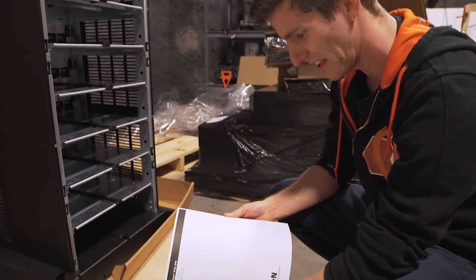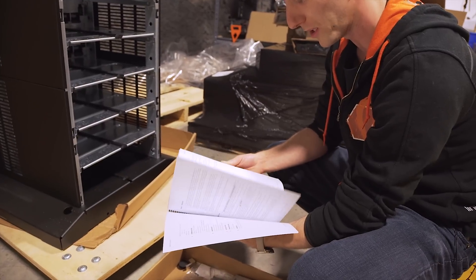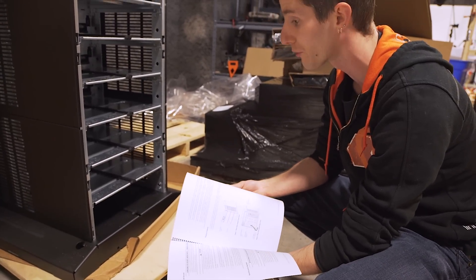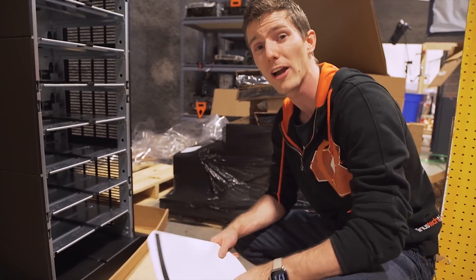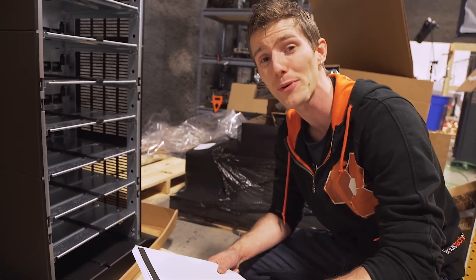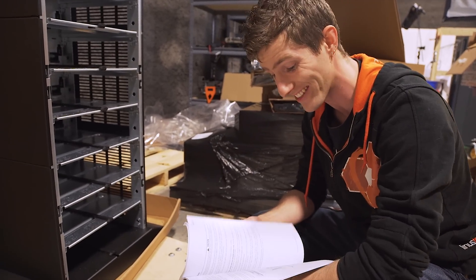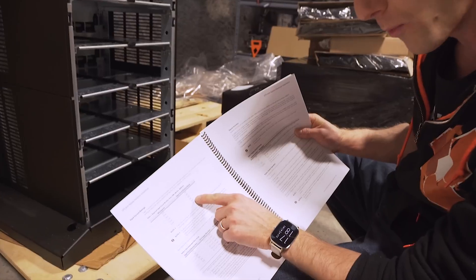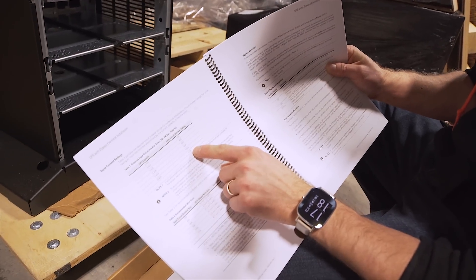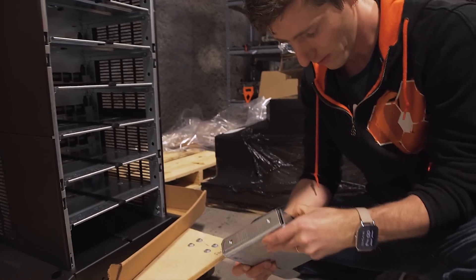Look at this user's guide — I don't blame them, this thing is not your simple plug-into-the-wall unit. In fact, with the 12 kVA unit we've got, we've had to wire up a completely separate 80-amp breaker and hardwire this guy into that. If you want one of the bigger units — the 15 or 18 kVA — you need a 100 or 125-amp breaker and an electrician to come wire it in.